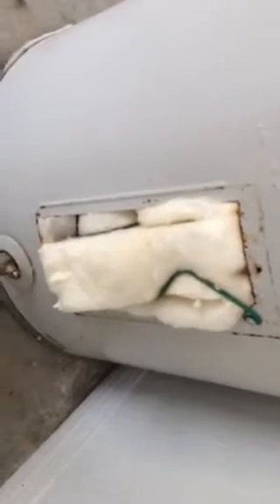And then when we further try to diagnose it, we can go in this panel and you can see that it's all rusty in there. I've caught this a few times with the thermal imager. Usually we don't dig in here, but when I see an issue with the thermal imager, then I can dig into it a little bit more. Thanks.